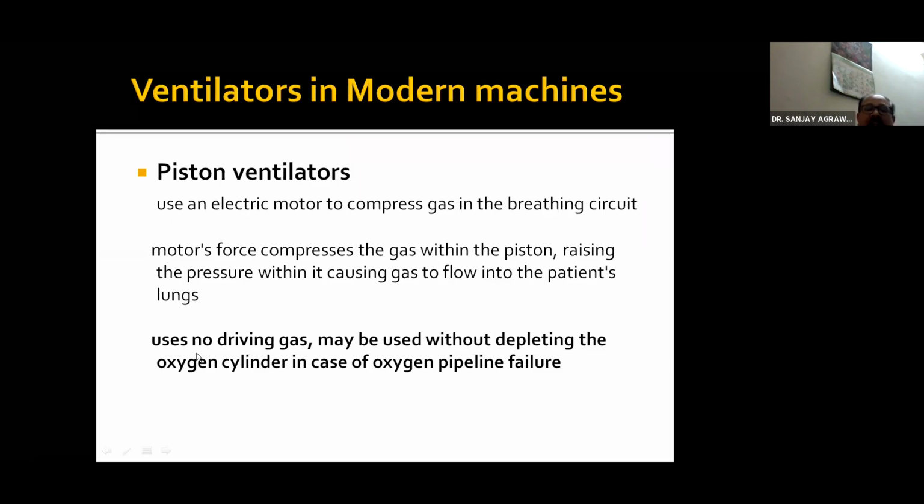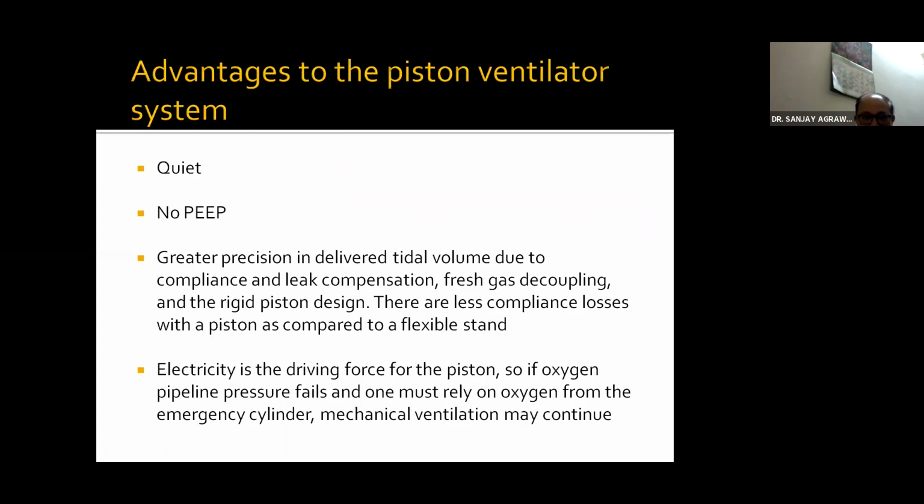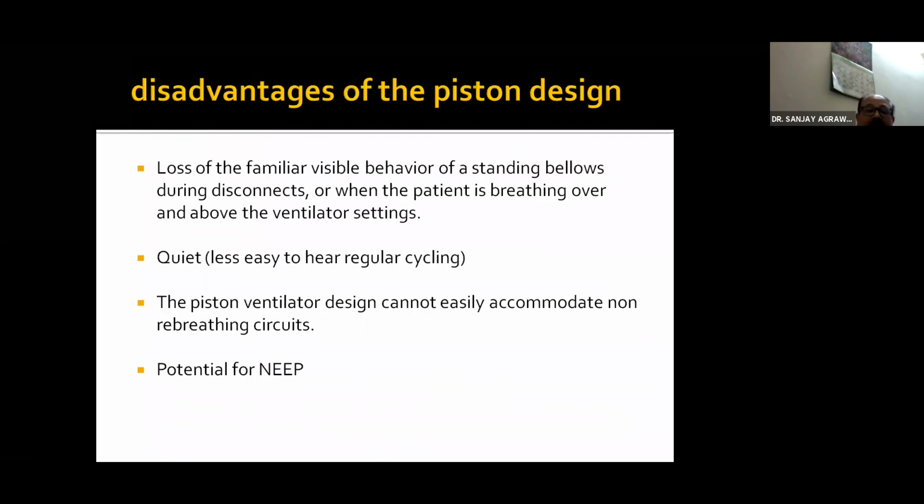And the other advantage is it does not use a driving gas. What I was talking about initially in bellows, it was the oxygen which was used as a driving gas. And it can be used even in conditions when the oxygen supply is on the lower side. Other advantages of the piston ventilators are that they are quiet, they do not generate PEEP, and there is greater precision in delivering the tidal volume. Electricity is the driving force, so oxygen is not used as a driving gas for the bellows to work. The disadvantage is that it is very quiet.